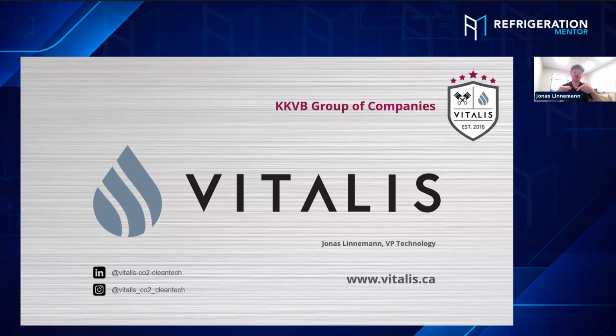Typically, these little tiny indicator strips or tests that turn a color are a good start. If you check the general color of the oil, the clearer it is, the better. If it gets dark, it's definitely time to change. So a visual inspection is very important. These quick tests that service techs have on hand help you understand if the oil needs to be changed immediately. What I also don't see regularly is a proper oil analysis from a lab, which turns this into predictive maintenance, because you can see if values from the lab change, like moisture saturation or other chemicals.